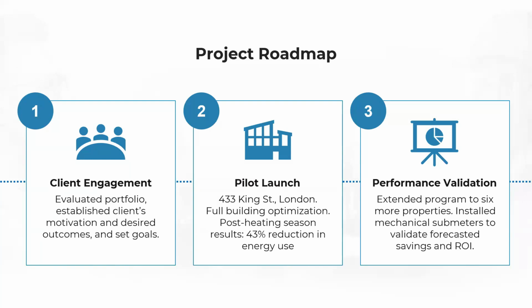But we drove down a 43% reduction in their predicted energy usage, not counting the new system, but on top of the new system that they were already putting in, because obviously a boiler chiller fan coil is much more efficient as a baseline than a PTAC building.